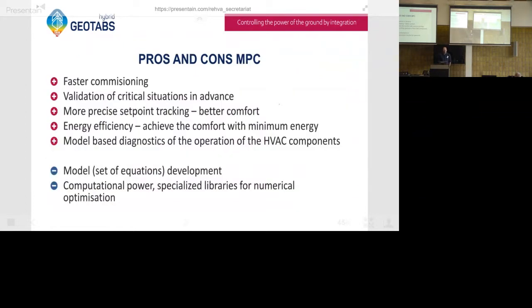What are the benefits and disadvantages of this approach? As already mentioned, once you have the model, commissioning of the MPC is very fast. Compare this to GEOTABS buildings, where it's very hard to tune the heating curve controller for supply water. With MPC, if you have a valid model with valid predictions, it's almost immediately implemented. But getting the model takes time, and that's the biggest disadvantage of this approach.